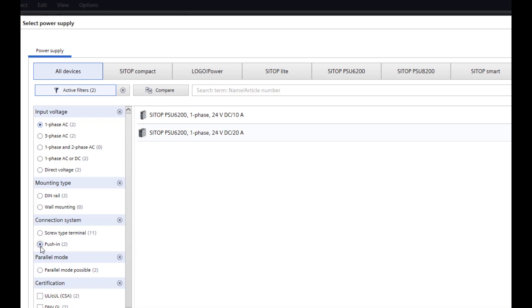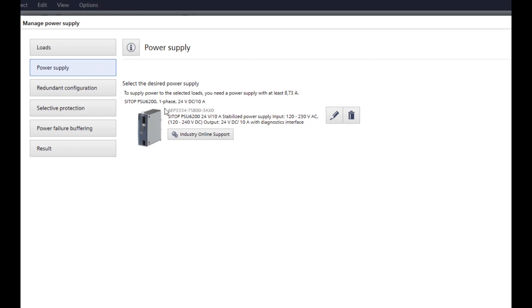The selection of the proposed devices is now significantly reduced and it could be chosen between the 10A or 20A variant. Due to the calculated load of 8.7A, PSU 6200 with 10A is the best choice. After selecting the device, the general information such as the designation and order number of the power supply is clearly displayed.